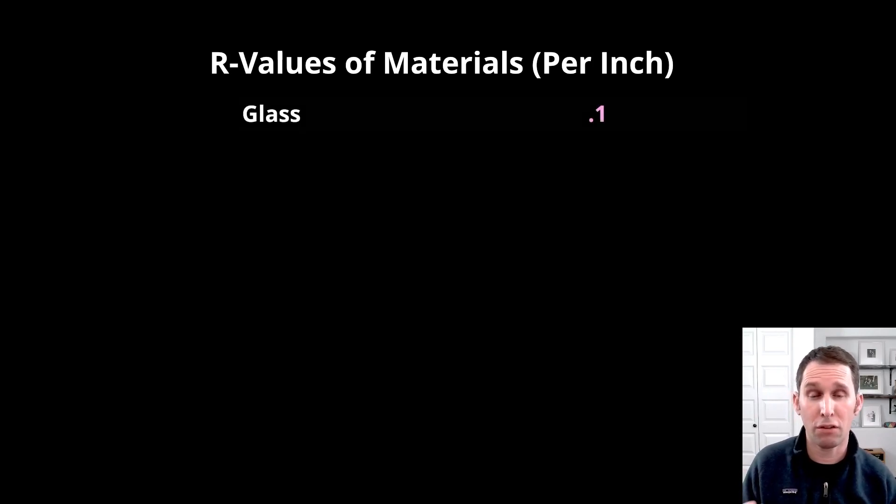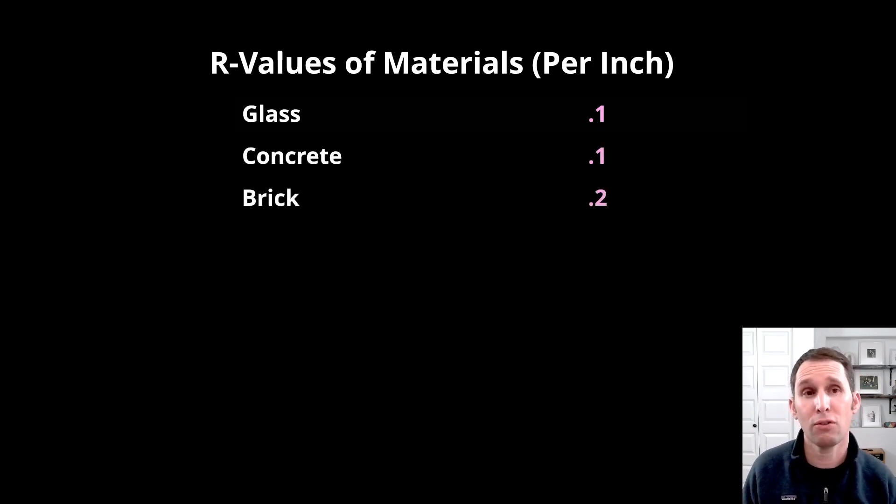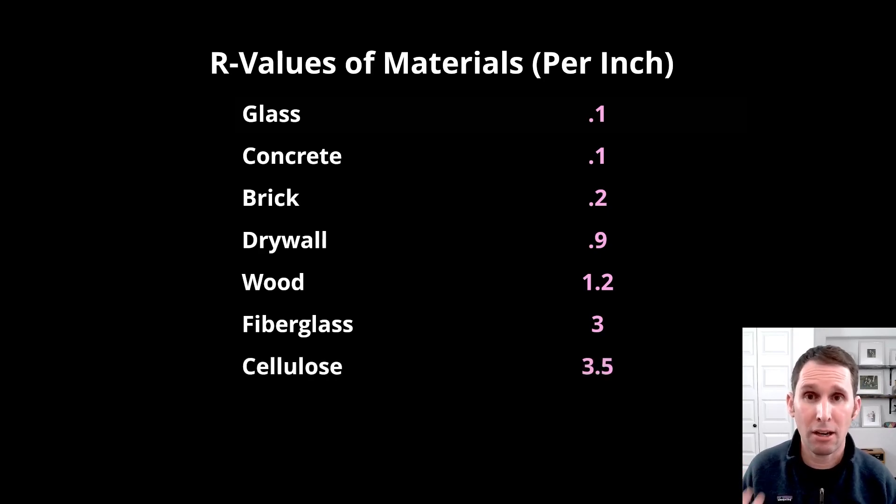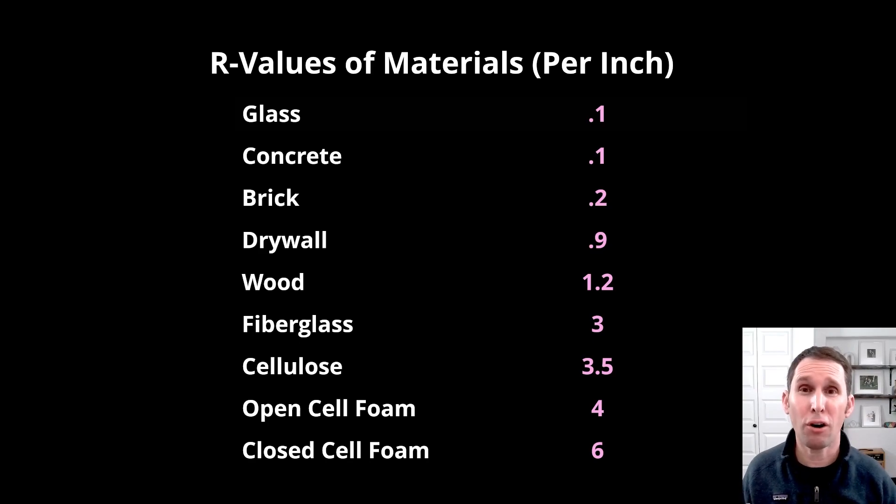So, if we take a look at a lineup here of different materials, you could see that glass is a very poor resistor of heat transfer. Concrete transfers heat very easily. Brick would transfer heat very easily. Drywall is a relatively poor resistor of heat transfer. So is wood. And then we get into the insulation materials like fiberglass, which is R3 per inch. Cellulose, which is R3.5 or R4. And even some foams like an open cell foam or a closed cell foam, which is R6 per inch, that would be 60 times more effective at resisting heat flow than something like glass.